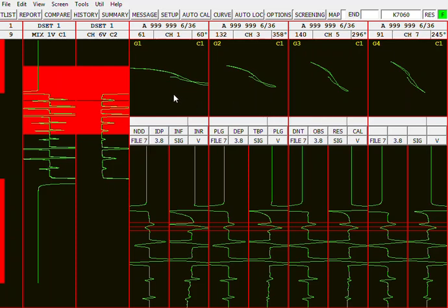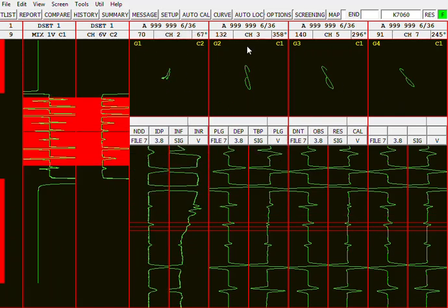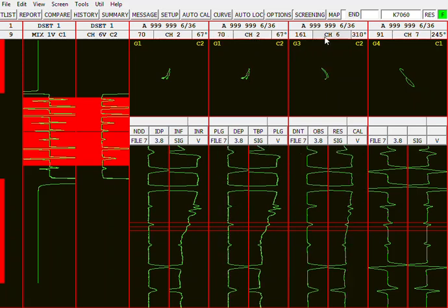So OD flaws and ID flaws both rotate towards the 100% hole signal as you decrease test frequency. So I'm going to click here so I can see my phase. That's 11 degrees, 24, 38, 43. This ID flaw is rotating clockwise with decreasing frequency, while the OD flaws are rotating counterclockwise with decreasing frequency. And the absolute channels will behave exactly the same way.